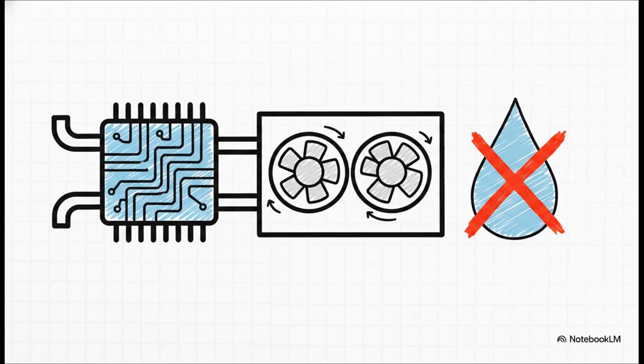They implemented direct-to-chip liquid cooling, literally capturing the heat right at the source. This allowed them to switch their outside heat rejection to a hybrid dry cooling system. And thanks to smart controls reading the outside weather, this entire facility can now run 100% dry, completely waterless, for 8 to 9 months out of the year.